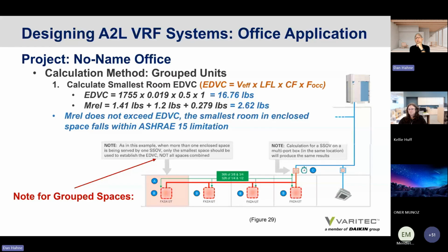Interesting. Okay. One other thing, Dan, because I know that you had, this is just another part that I didn't see on a slide, but UL does allow indoor units up to 10 tons. And so there's another addenda, which is under review by ASHRAE, which will allow indoor units up to 10 tons.